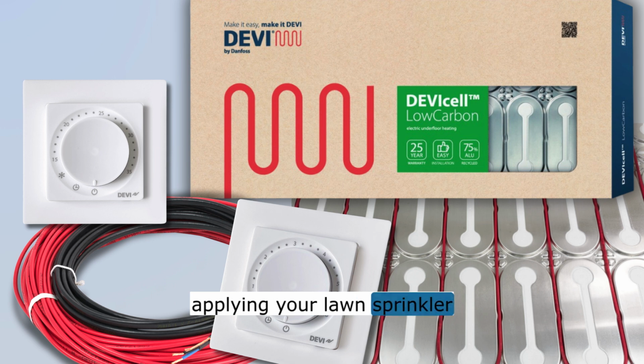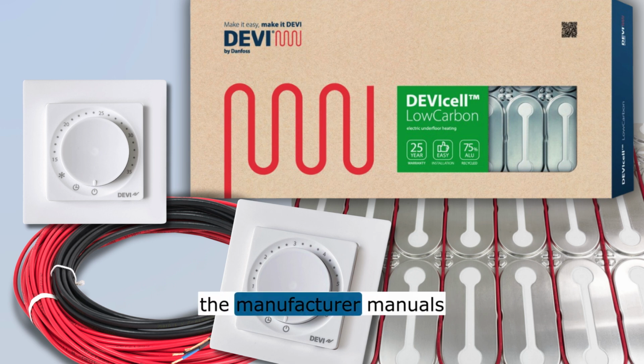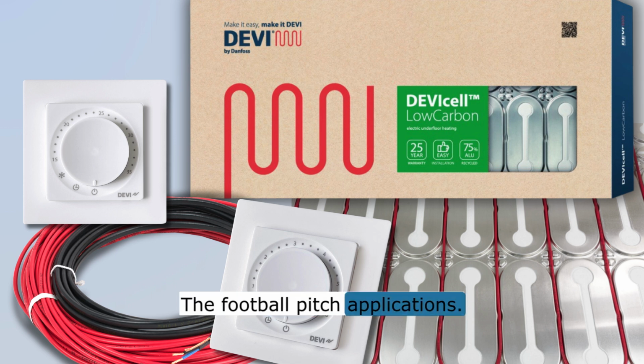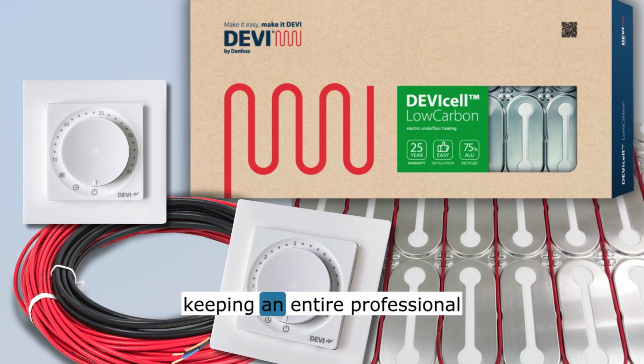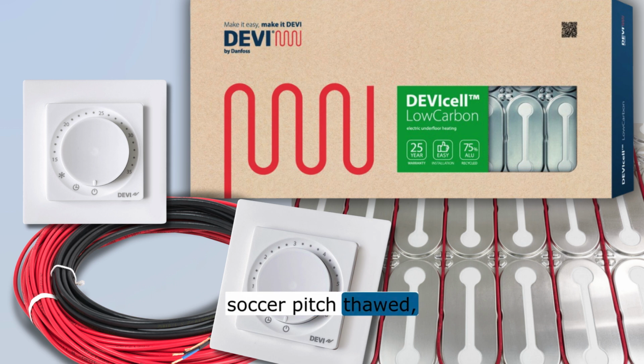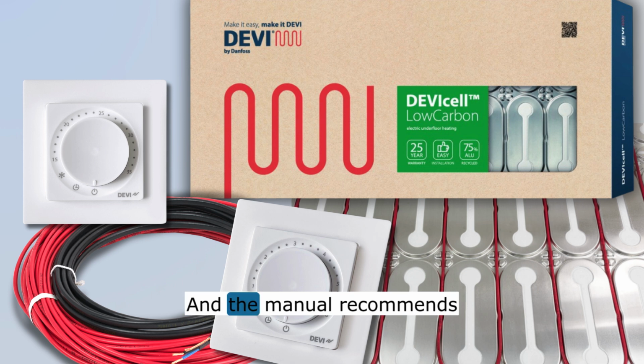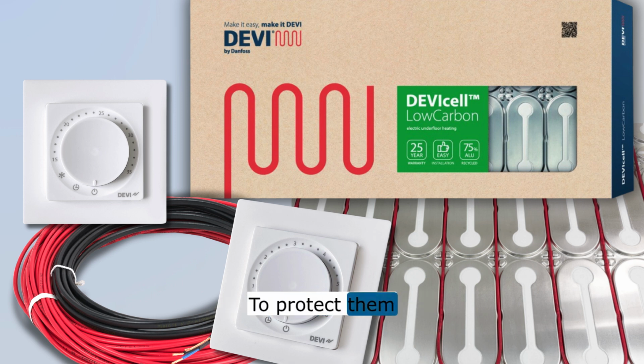Now, applying your lawn sprinkler analogy to a massive scale, the manufacturer manuals actually provide specs for outdoor football fields. Oh yes, the football pitch applications. And wild to think about, we are talking about keeping an entire professional soccer pitch thawed, soft, and green in the dead of winter. For a project like that, the CC distance is typically tight, around 15 to 25 centimeters. But the golden rule for sports fields is that the CC distance must be equal to or less than the installation depth. And the manual recommends burying the cables 25 to 30 centimeters deep. Right, to protect them from the massive tractors and aerators they use to maintain the turf.